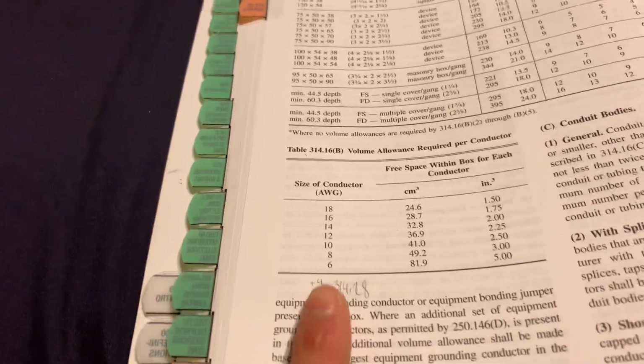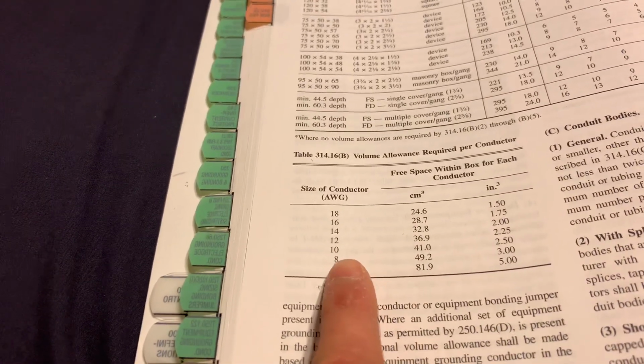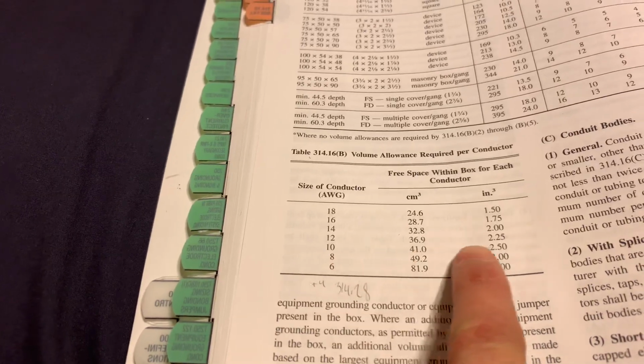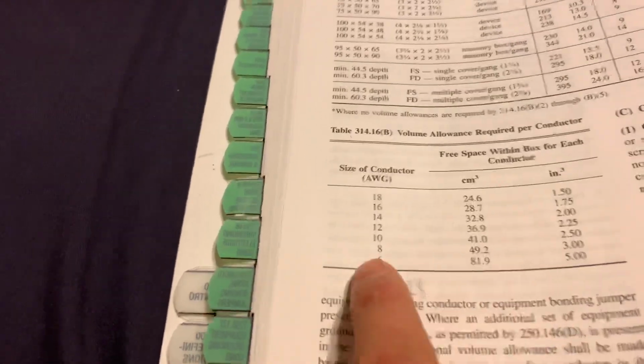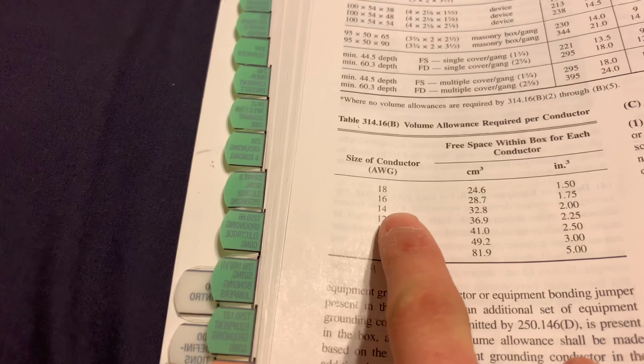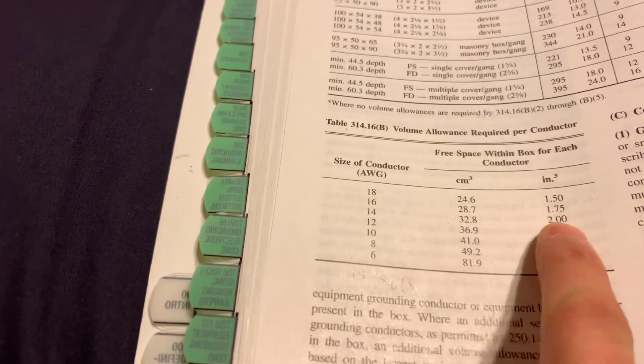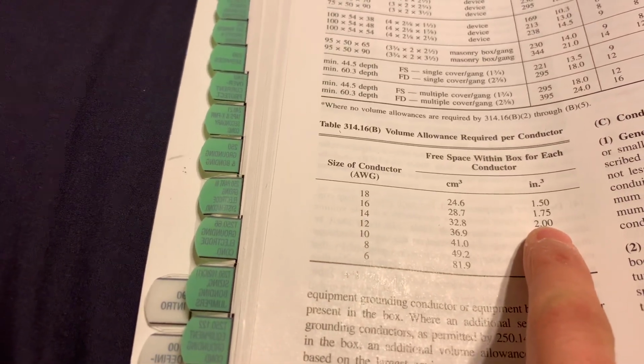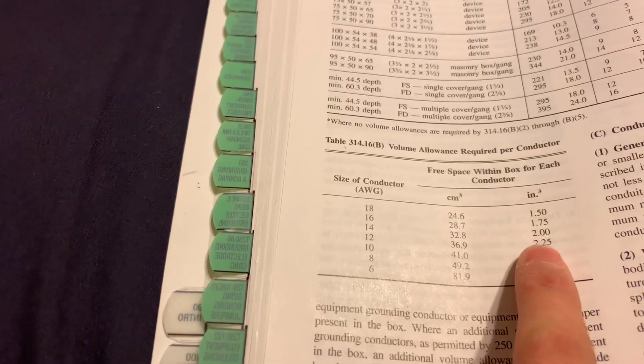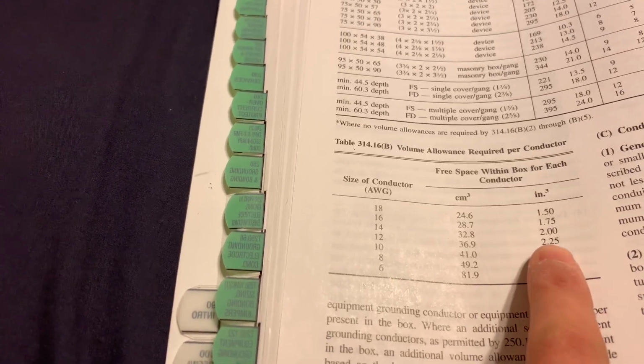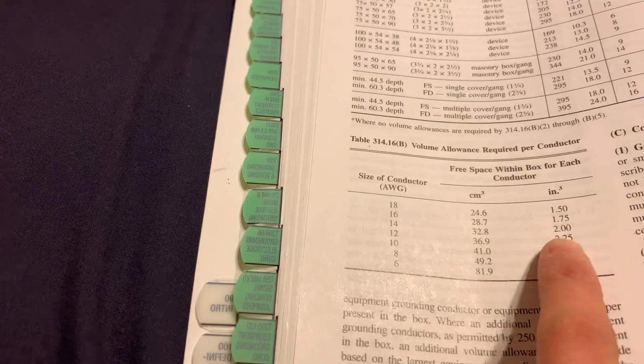So basically what that means is each wire has a value. If you have a 12 wire, it's 2.25, but just for the sake of being easy right here, we'll go 14 wire, and that's good for 2 cubic inches, and I believe that's for the hot and neutral. The ground is counted once, I think.